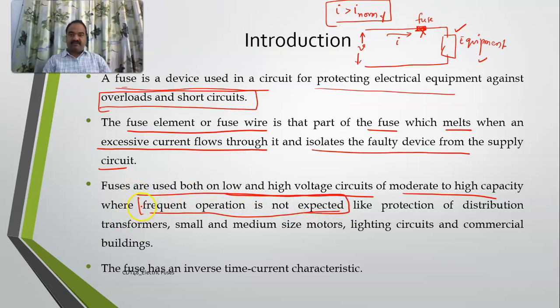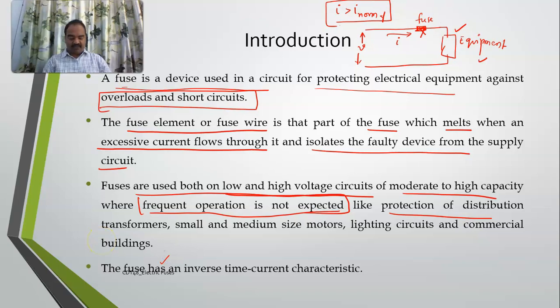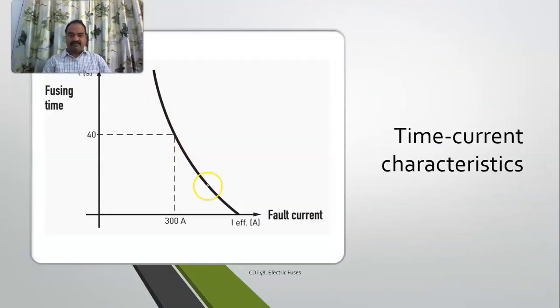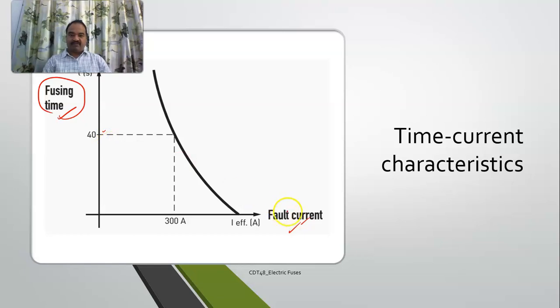Fuses are used where frequent operations are not expected, in applications like protection of transformers, motors, lighting circuits, and commercial buildings. Moreover, a fuse has an inverse time characteristic. In this characteristic, the x-axis is the fault current and the y-axis is the time of operation. If the fault current is low, it may take a longer time, but if the fault current is high, the fuse will act immediately.